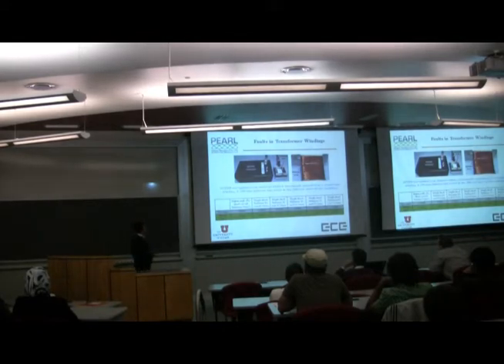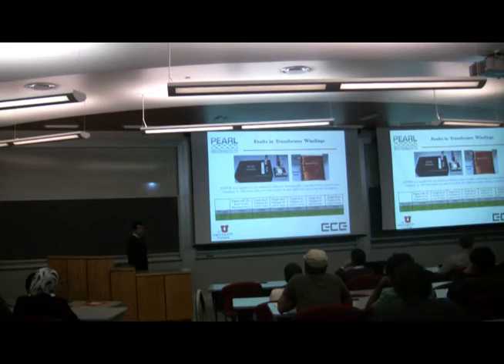We also tested a transformer winding when we created a short circuit between adjacent windings. And the SSTDR circuit can detect this, the location and also the amount of short circuit. So we tried it on two different transformers. One is an air-cooled transformer, no core, and the other is a transformer with core.